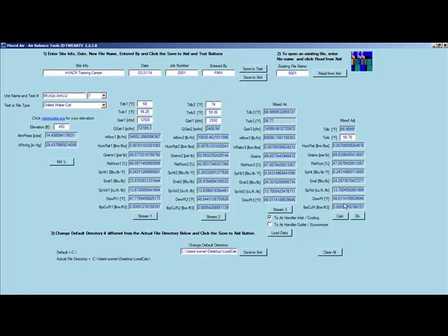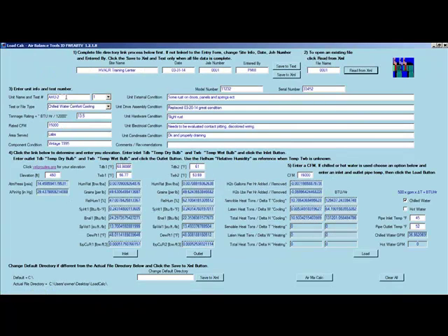If I go up to 0.8, 49.67, I'm over. So let's bring that to a 7. And we'll say 6.3. As we push this over, we would actually load this data to our air handler number 2, which is there.